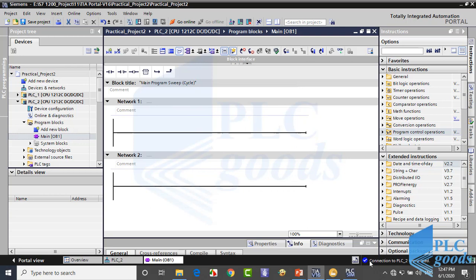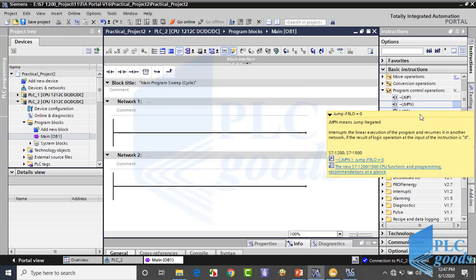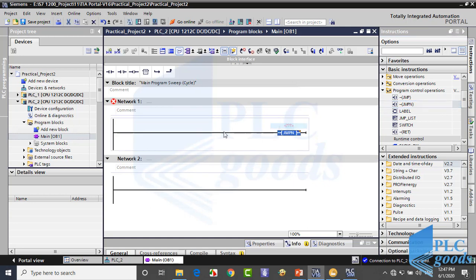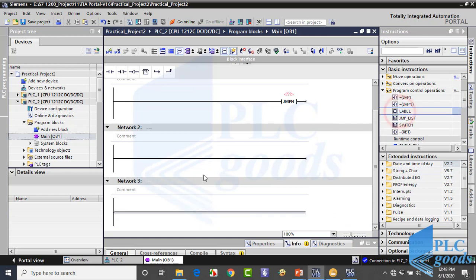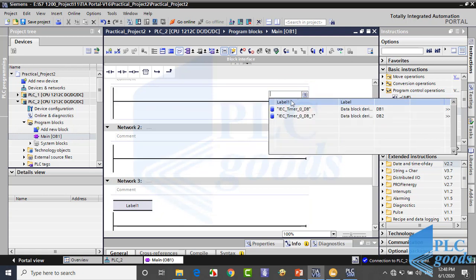Let's write a simple program to see how we can use these instructions. Here are the program control operations. The jump instruction has been shown. The next instruction is jump negative — it's like simple jump but it works when the RLO is 0. The destination network must be identified by a label. We can use the label instruction to identify a destination network in which the program execution should resume when a jump is executed. Now I can refer to label 1, which is placed in the third network.